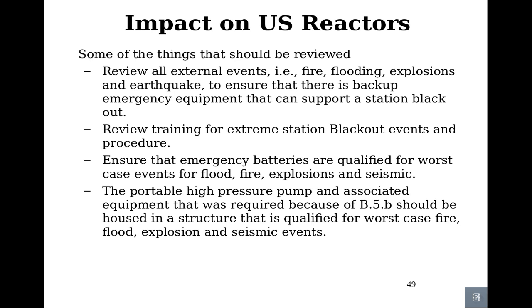B.5.b requirements include a review of all external events, including fire, flooding, explosion, earthquakes, to ensure that there is backup emergency equipment that can support a station blackout. Further, one should review training for extreme station blackout events and procedures. Ensure that emergency batteries are qualified for worst-case events for flood, fire, explosions, and that there are portable high-pressure pumps and associated equipment that is required for core cooling.